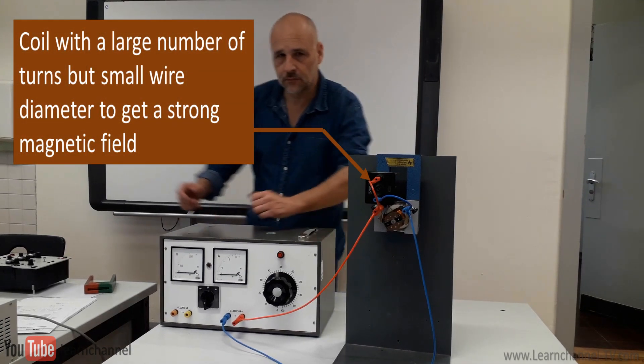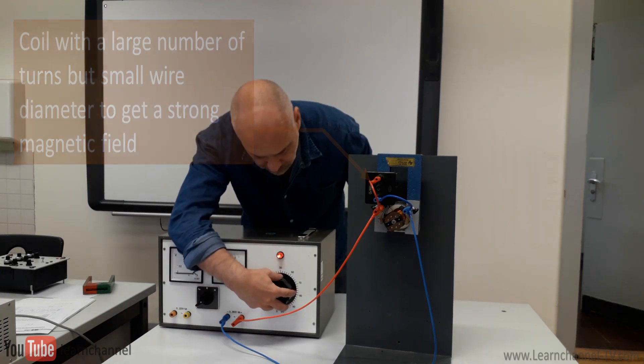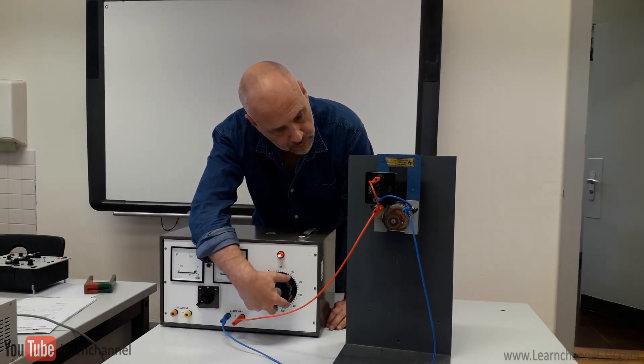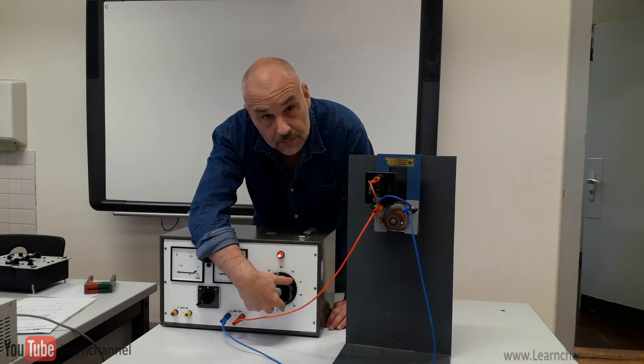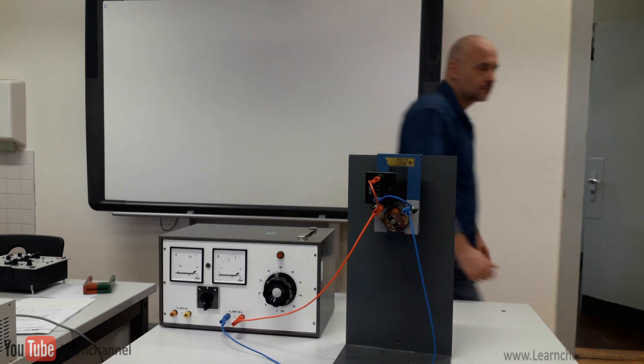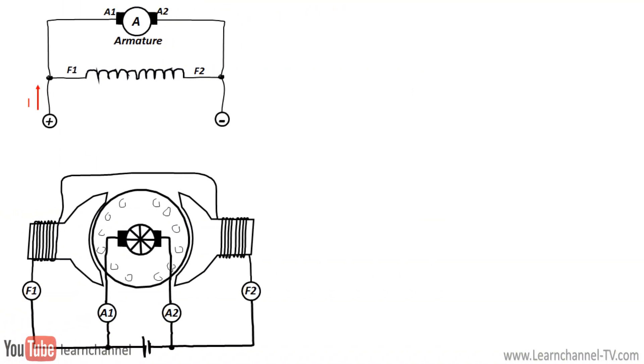Connect the armature winding in parallel to the field winding, you get a DC shunt motor. The field winding consists of thin but many turns to achieve a strong magnetic flux, so both winding are exposed to the same power supply. This motor is able to maintain a constant speed with any load, but how so?